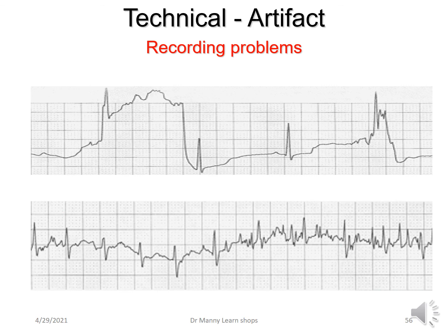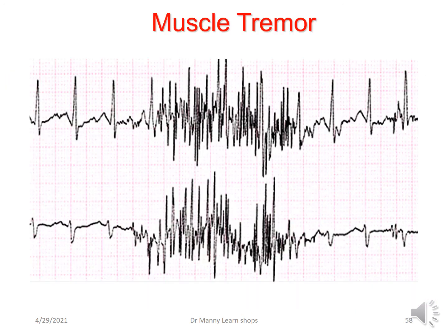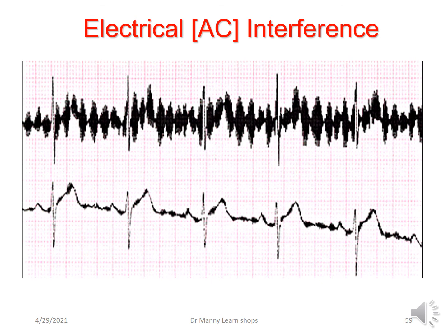When it comes to recording the ECG, often there are technical problems — problems you encounter when recording. There are three main ones here. First, a wandering baseline, which is due to movement, loose connections, or incorrectly connected electrodes. Second, muscular tremor — also referred to as somatic tremor — the patient is shivering, moving, has Parkinson's disease, is cold, nervous, or restless. Third, AC interference coming from faulty electrical equipment, which means you need to call your bioengineer, because you cannot interpret this ECG as it is.